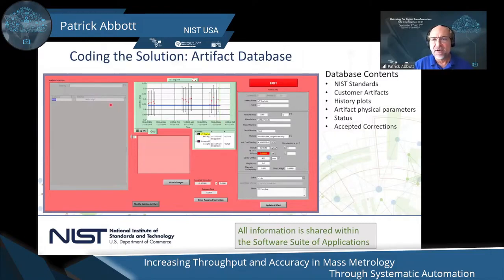And then for that given artifact, there is a list of all of its parameters: its nominal mass, its correction value, accepted correction value, its density, its volume, coefficient of thermal expansion, its center of mass. All of these things are available for entry, for modification into the database. So we use this for both NIST standards and also for customer artifacts. And it allows us to have history plots and all these other things that I've just mentioned, and to share it with the software suite of applications that were created.